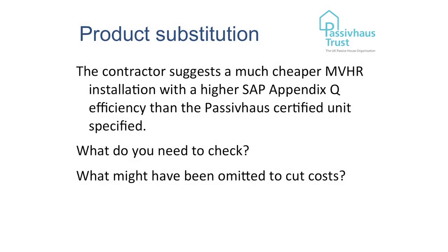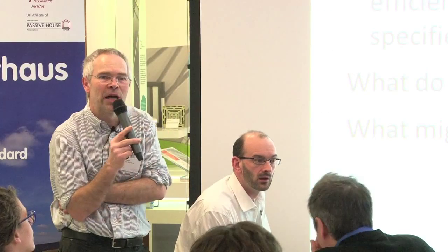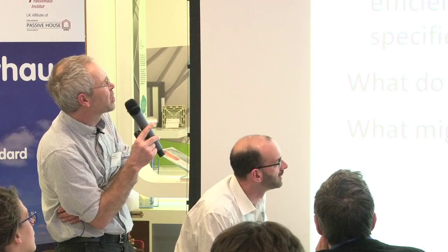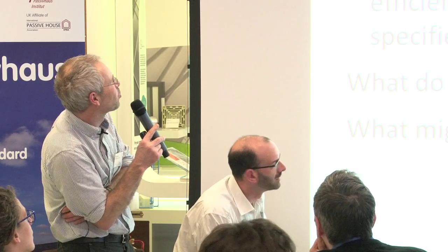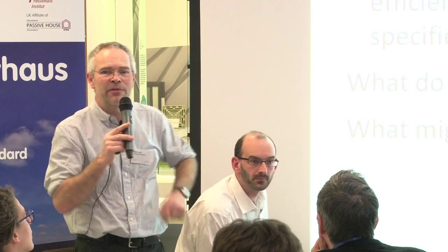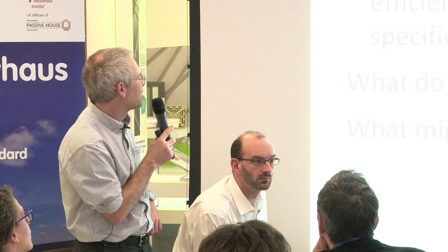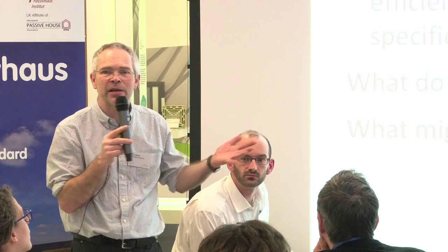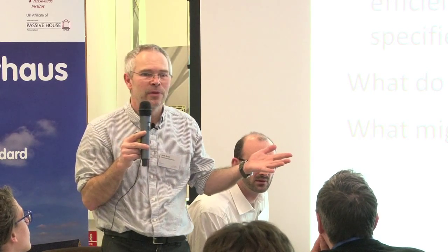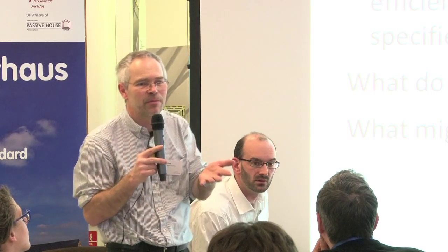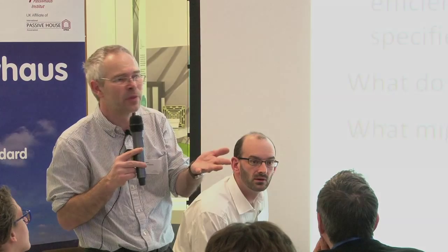The contractor suggests a much cheaper MVHR unit with a higher efficiency than the passive house one you specified. So what do you need to check? It's a whole system they've offered — a much cheaper system installed. What might they have chopped out? There are two things to check: efficiency and fan power — and also noise.